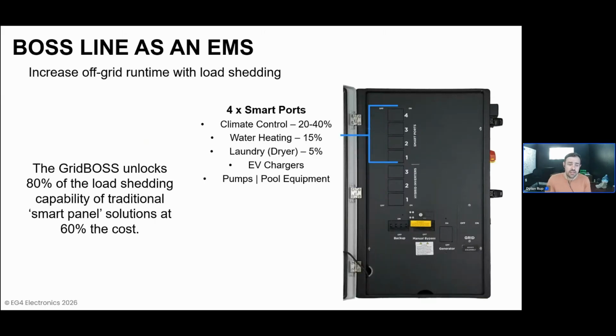The BOSS line is both an energy management system, an EMS, as well as a power control system. And that does a couple of key things for you to streamline compliance and streamline deployability. We already talked a little bit about the load shedding capability of the GridBOSS, but I think it bears repeating that acting as an energy management system to intelligently manage the loads on site, this GridBOSS can reliably increase the off-grid runtime of an energy storage system by as much as 40 to 50%. And it's going to do so at less than 60% of the cost of a traditional smart panel solution that you might see deployed alongside an energy storage system. And that's before you consider all the additional functionality that we talked about with the GridBOSS.